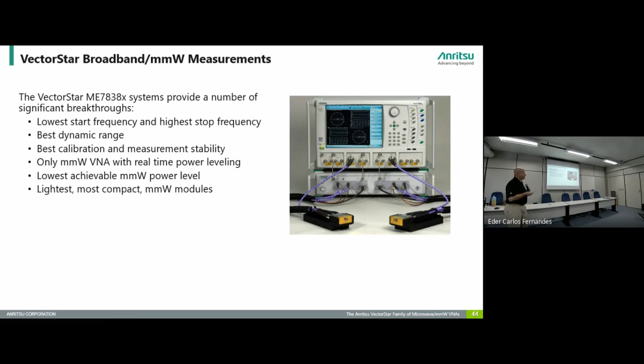And now we're going to talk about an area that also is expansion of your current system, and that is optoelectronics. There's no reason why, when we're characterizing electrical devices, that we can't also characterize the frequency response of electro-optical devices. As long as we can get back to electrical, the VNA is happy. We need to be able to convert back to electrical so that we can do a standard calibration, and then we can de-embed or remove the part of the setup that we're not interested in. Usually it's the reference. We designate a reference and then we remove it from the combined measurement.